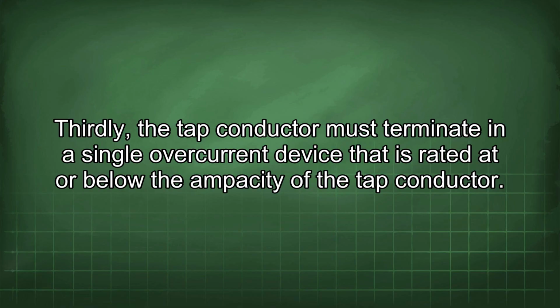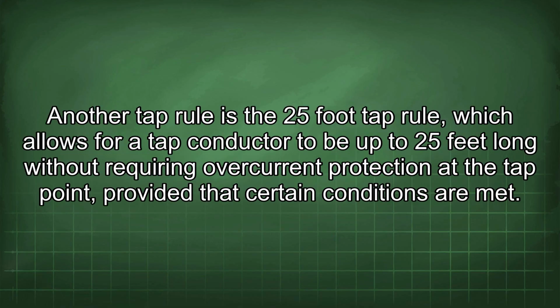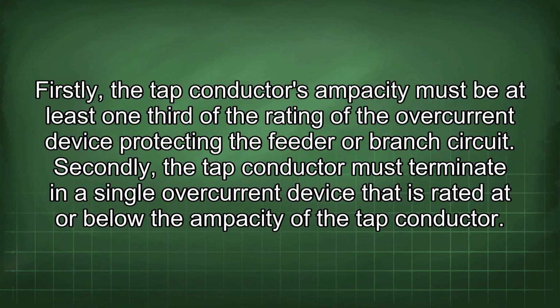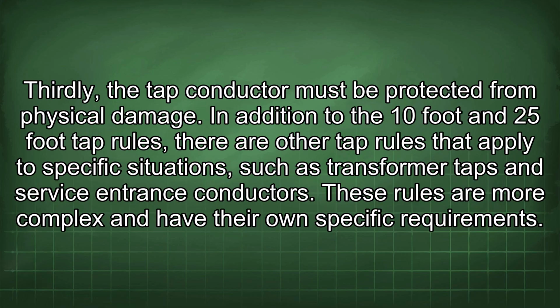Another tap rule is the 25-foot tap rule, which allows for a tap conductor to be up to 25 feet long without requiring overcurrent protection at the tap point, provided that certain conditions are met. Firstly, the tap conductor's ampacity must be at least 1/3 of the rating of the overcurrent device protecting the feeder or branch circuit. Secondly, the tap conductor must terminate in a single overcurrent device that is rated at or below the ampacity of the tap conductor. Thirdly, the tap conductor must be protected from physical damage.